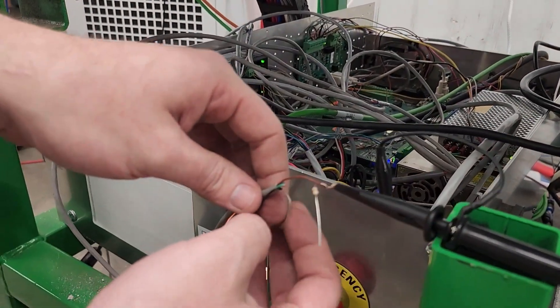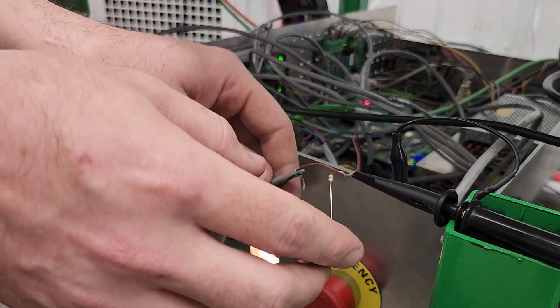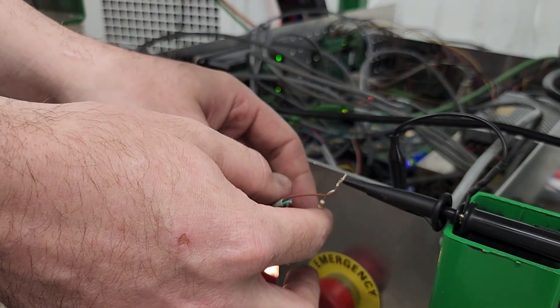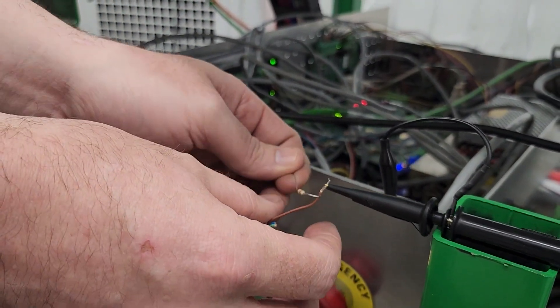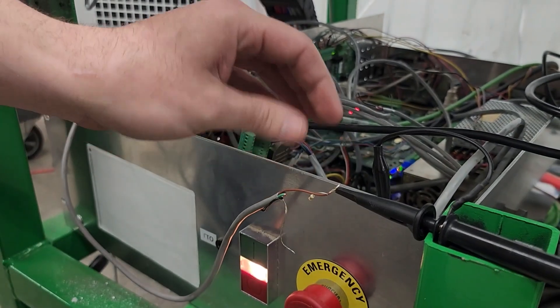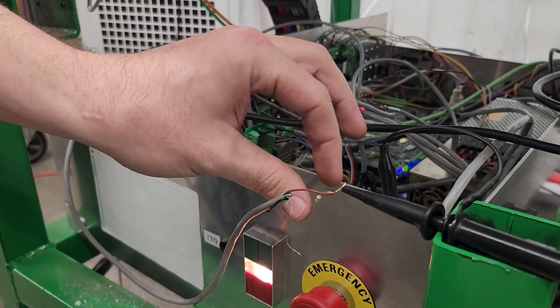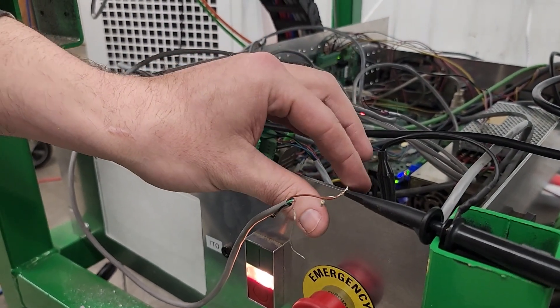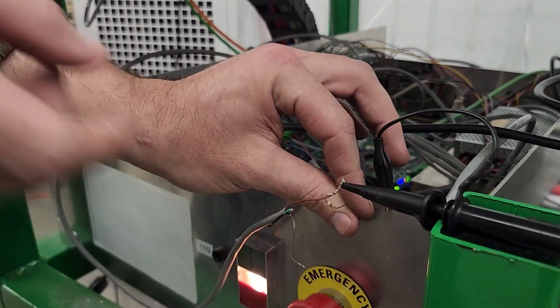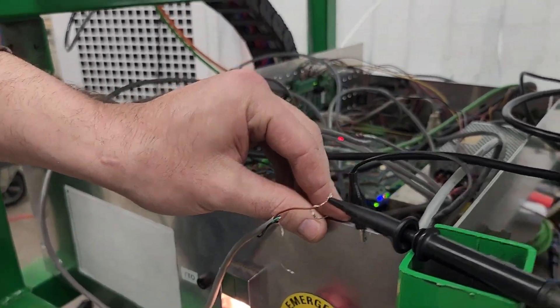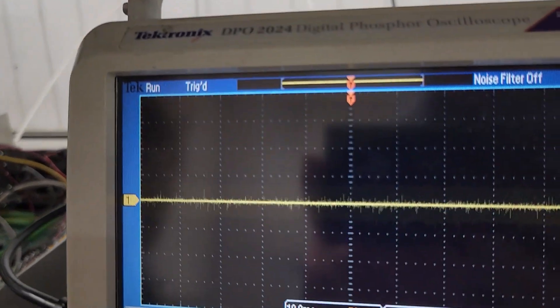Now we also have a resistor here, and we're going to do the same thing. With a resistor in parallel, we're going to drain off, or the resistor is going to remove that interference from the line. I'm just going to connect that resistor to the cabinet also. You can see it clean up. Maybe not near as clean.